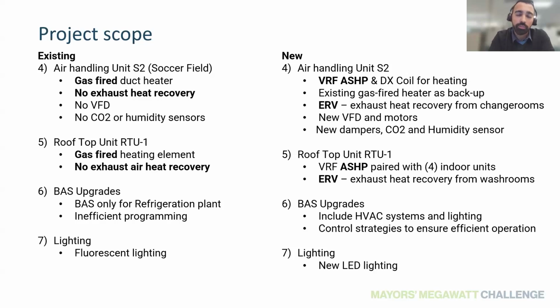Unlike what we anticipated initially, we didn't have enough waste heat to supplement all the heating systems in the building. So we used that strategically for the ice rink as well as the domestic hot water. Then for the third avenue, we utilized air source heat pumps and energy recovery ventilators to recover as much as possible, basically making the processes as efficient as possible.